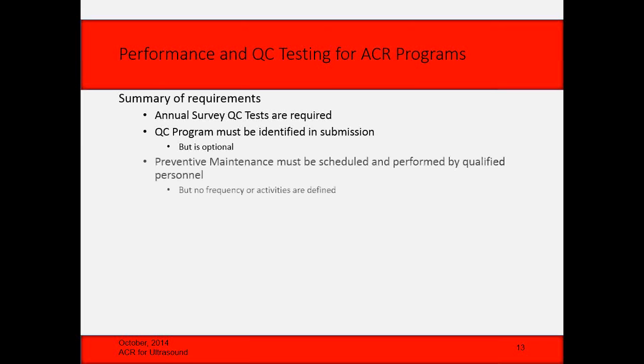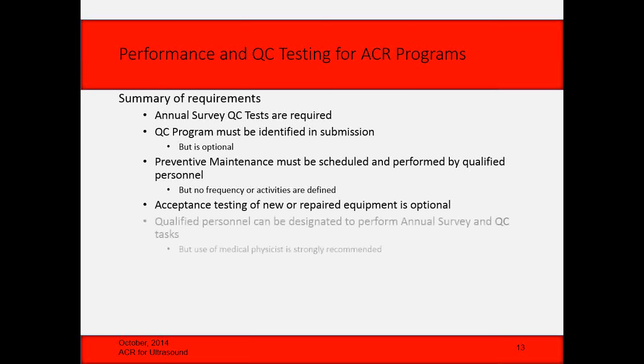If I was submitting, by the way, under those conditions, I would probably take a scan of the page of the Sonosite manual that says no PMs are required and attach that to the submission. Acceptance testing of new or repaired equipment is now optional. Qualified personnel can now be designated to perform the annual survey and the QC test.